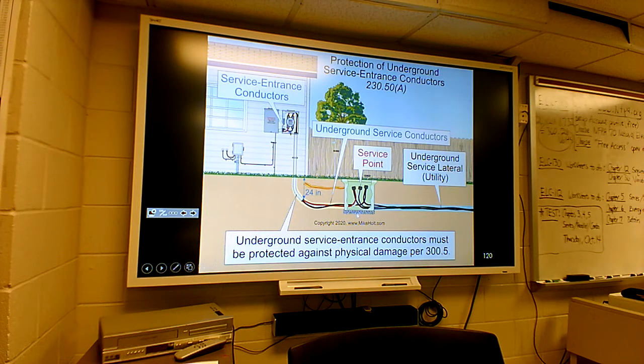So now if you notice here, they got conduit coming out of your service there, going underground for 24 inches. And then it's actually just direct buried from that point there. Now, when they put my generator in the house, I had a generator put in, automatic transfer switching off. When they installed it, they did like that. They did the conduit where it got under the ground, and then from then on out, it was like direct buried conductor, because the wire is actually listed to be direct buried, and you want protection down to say 24 inches below the surface. And then from then on out, it's not bare wire buried. It's listed, and that's the way they do it.